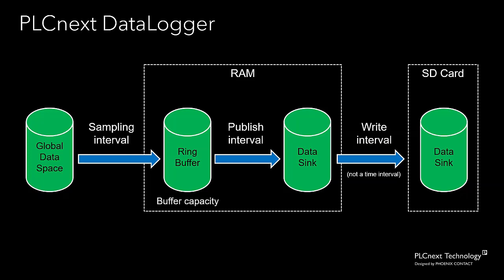But how do we choose values for these parameters? Let's take an example. If we have a sampling interval of 100 milliseconds, that means we're sampling variable data in the global data space 10 times a second and moving that data into the ring buffer. If we set the buffer capacity to 10, that means that after 10 samples are stored in the ring buffer, the oldest values will start getting overwritten with newer values. So from a time point of view, the buffer has a capacity of one second. That means we have to move data from the ring buffer into the in-memory data sink at least once a second, so our publish interval has to be less than or equal to 1000 milliseconds.